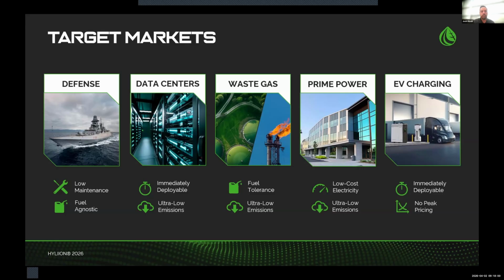The last one I'll highlight is waste gas. As mentioned in the short video, we can use highly diluted fuels, mixes of fuels—all of that is completely fine. In a landfill application, or maybe a digester where the fuel is infinitely variable and changing all the time, that's really not an issue. Our system can take that, adjust its flow rate depending on the fuel being provided, and still get you your electrical output in the end.